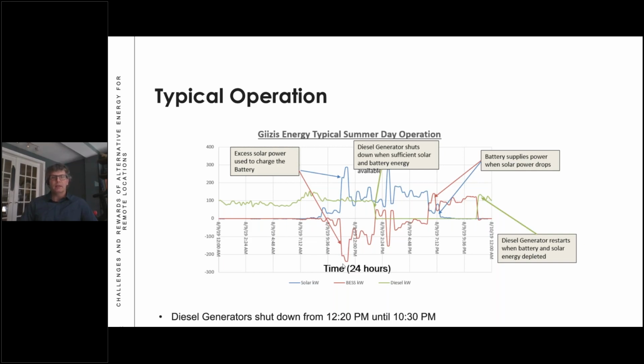If the battery is below the line, that means it's charging; above the line is discharging. Typically, through the night, diesel generators provide all the power for the community. Morning comes, sun comes up, the diesels go to their minimum operating point, which is about 40% of whichever diesel's online. And as the amount of solar energy goes above what the community needs, we charge the battery.